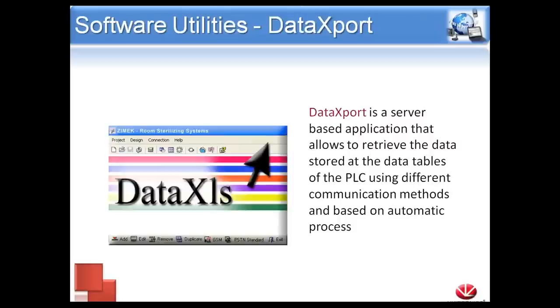DataXport will connect to a controller or a group of controllers on a schedule that you set up and log any information on the controller. We can gather all the information from all the data tables, grab any group of operands, and store this information on a remote server or your PC as spreadsheets in Excel files. For example, in a manufacturing application, we can set up DataXport at 8 o'clock every day to connect to the controller, grab the numbers for the day, and save them in a spreadsheet — as long as DataXport is running, we'll always have that record.